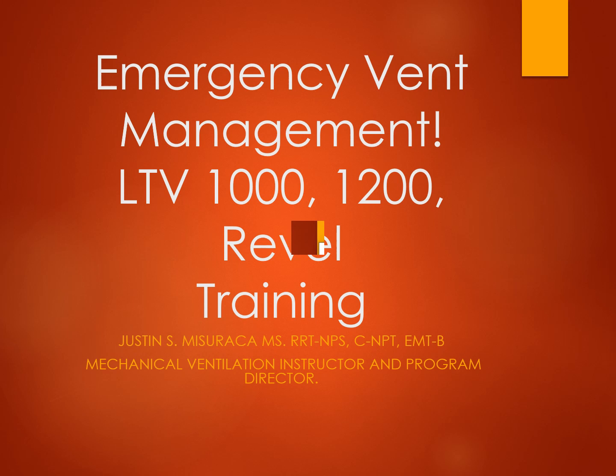So you really have to make sure that you're being careful with that number. That could really cut into your volume. And if you're transferring a patient, you have the settings the same, you could literally be cutting that patient's volume in half by not paying attention to the rise time. This is one of those numbers when people in the back screen, they set it when they're training somebody and they forget to put it back. And if they forget to put it back, that's when you get in trouble.